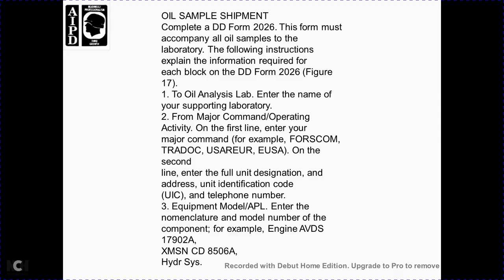Oil sample shipment must be completed with the DD Form 2026. The form must accompany the oil sample to the laboratory with the following instructions. Here is the information required in each block of the DD Form 2026, Figure 17.